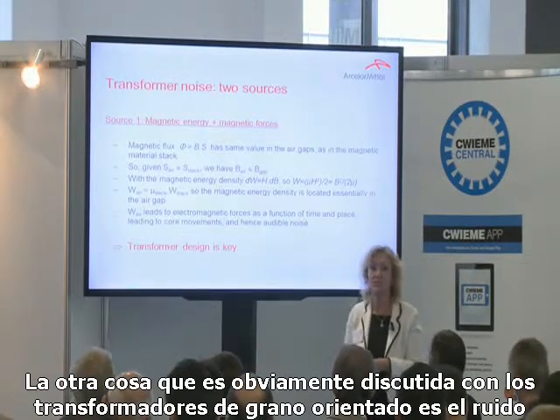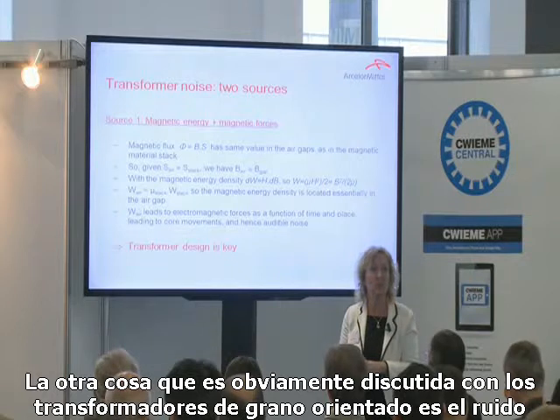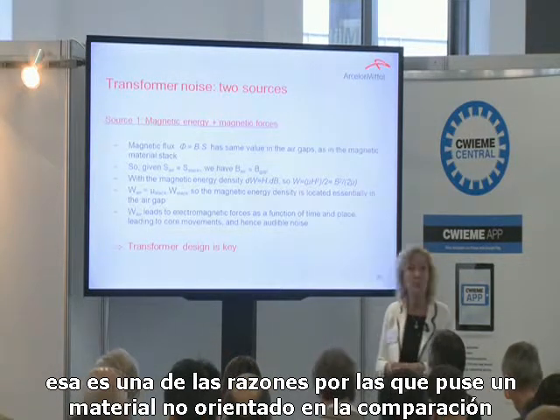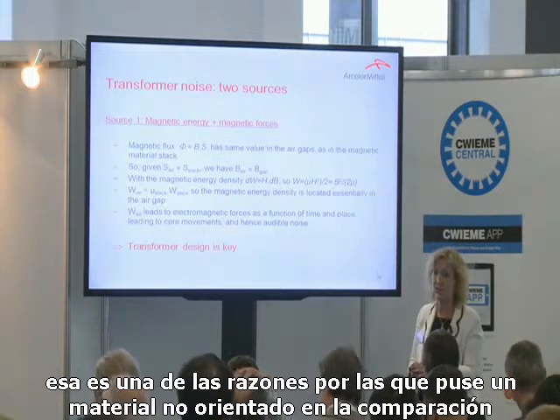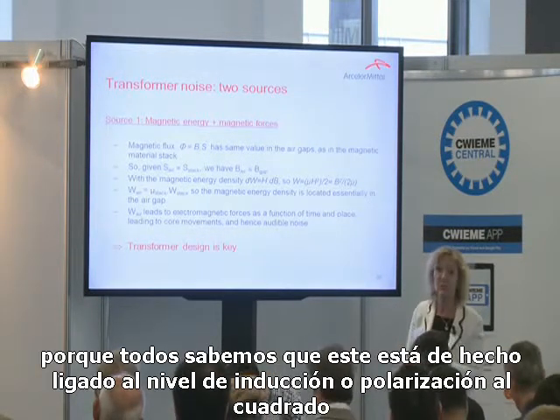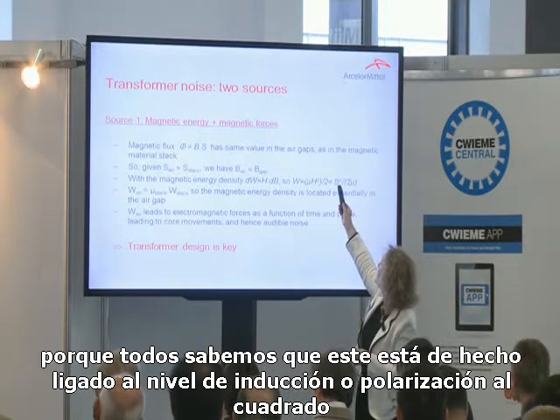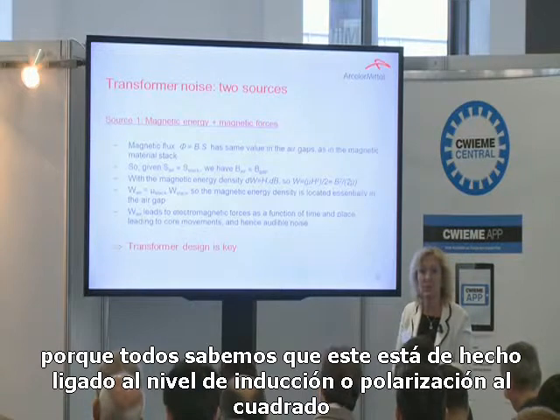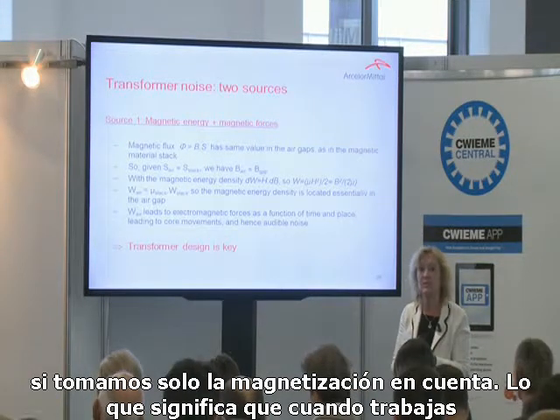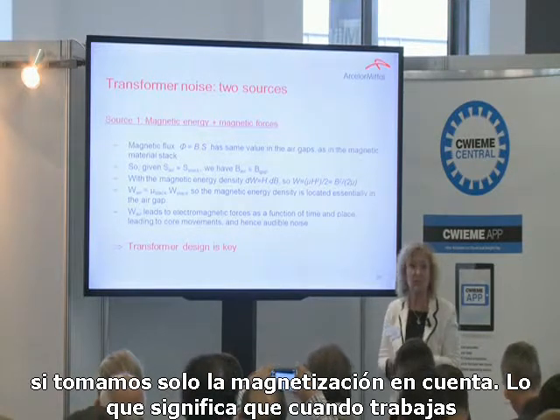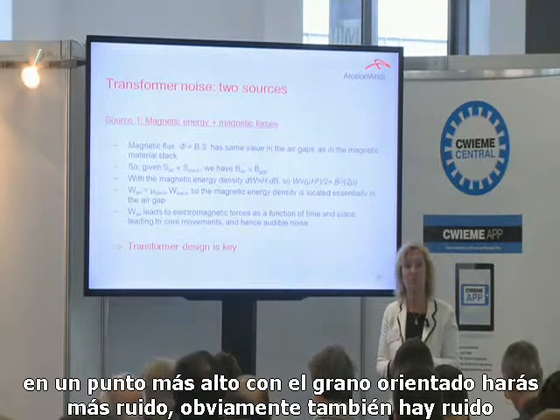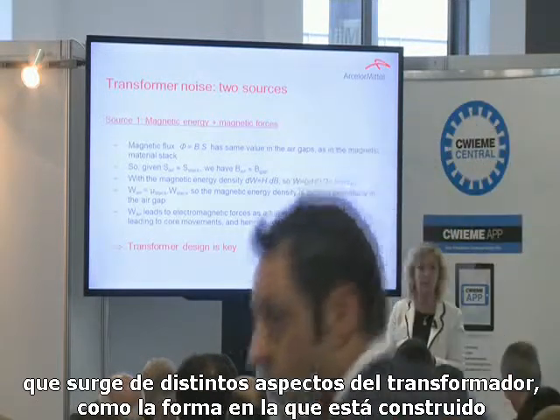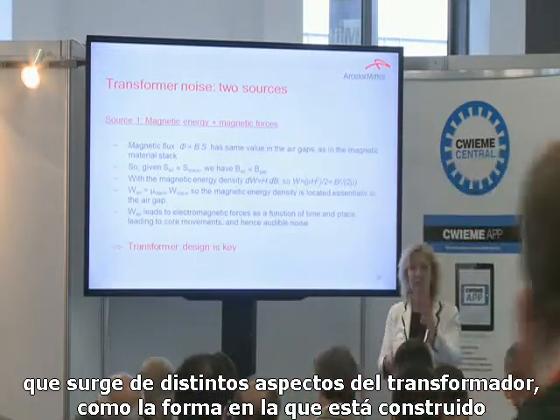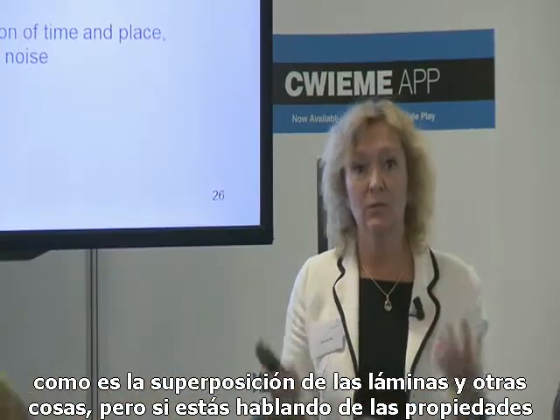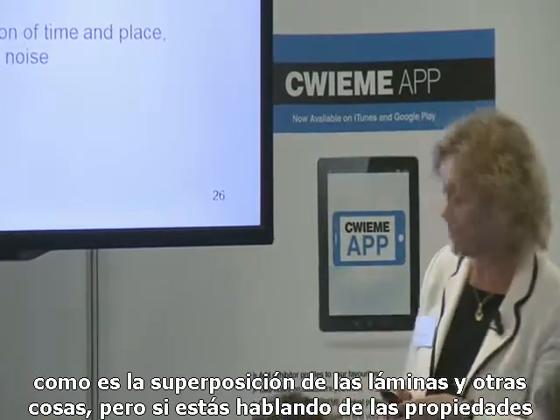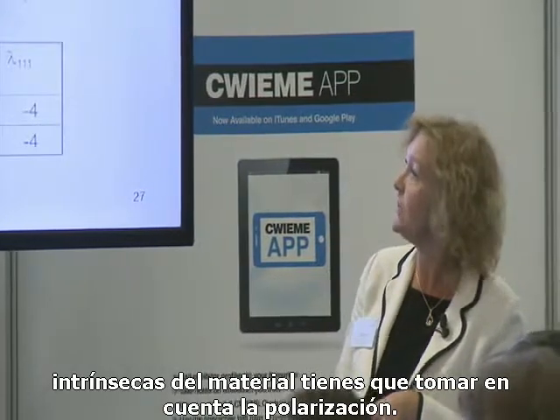The other part often discussed regarding grain-oriented transformers is obviously transformer noise. That's one reason I put a non-oriented material in the comparison, because we all know the noise is linked to the induction or polarization level squared, if you just take the magnetization forces into account, meaning that when you work with a higher working point in a grain-oriented material you create more noise. There's also noise from other aspects, such as how the transformer is built, how the overlap is done in the laminations, and so on. But if you want to talk about intrinsic material properties, you have to take the polarization level into account.